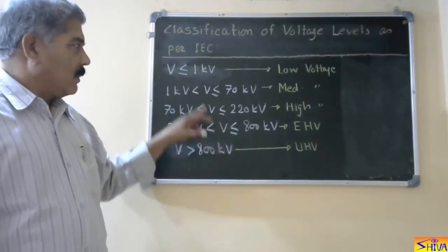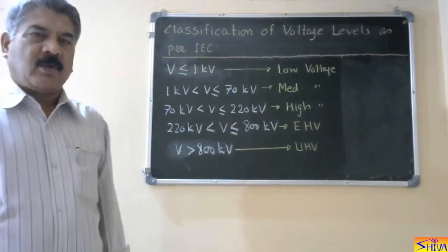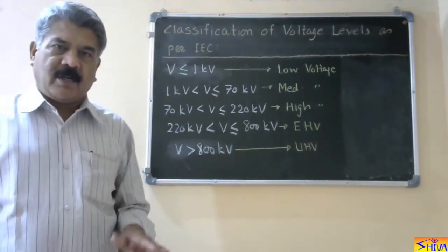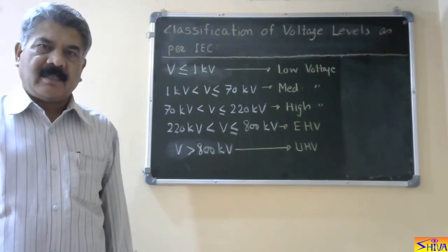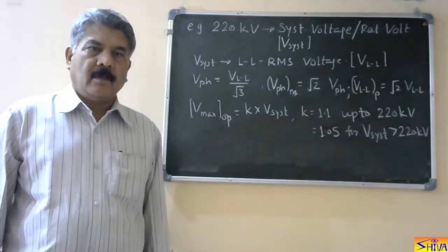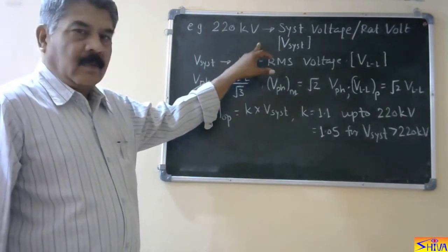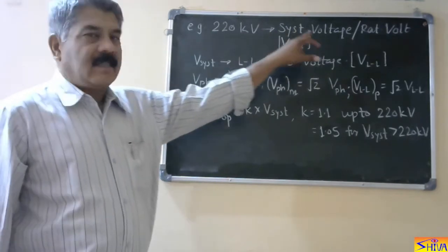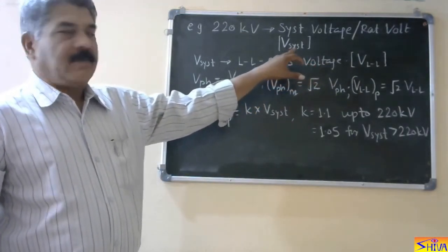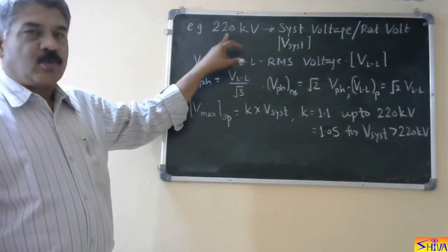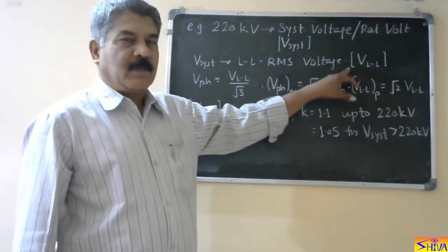An important point: these voltage levels specified are line-to-line voltage and RMS values. So if we consider a 220 kV line, then 220 kV is the nominal or rated voltage of the system, and that 220 kV is the RMS line-to-line value. We can denote this as V_system, which equals V_line-to-line.